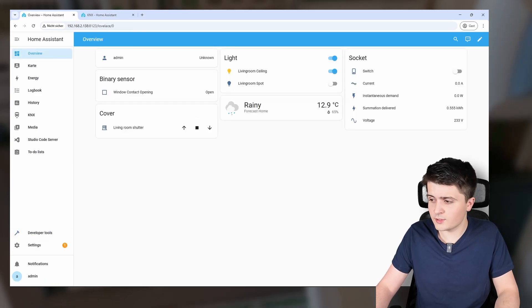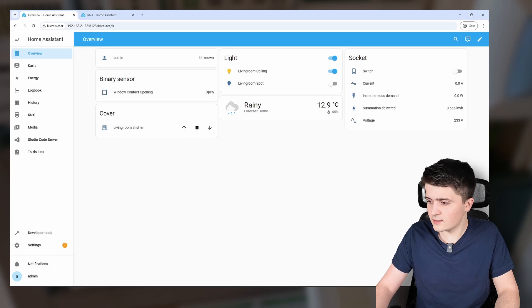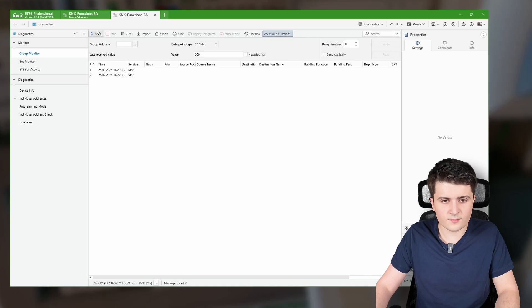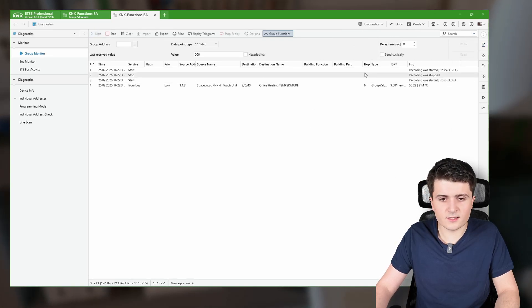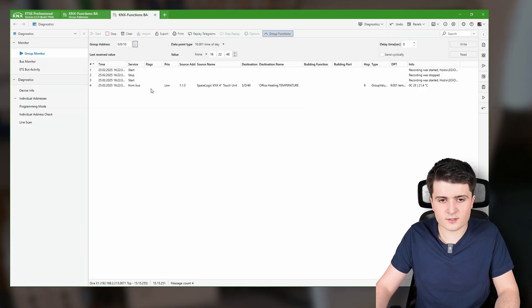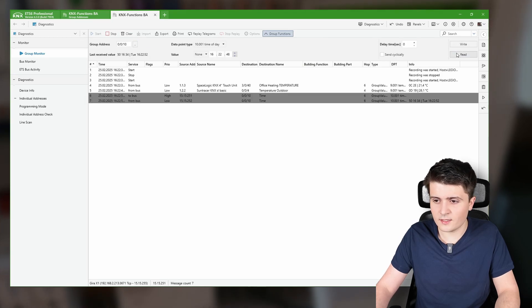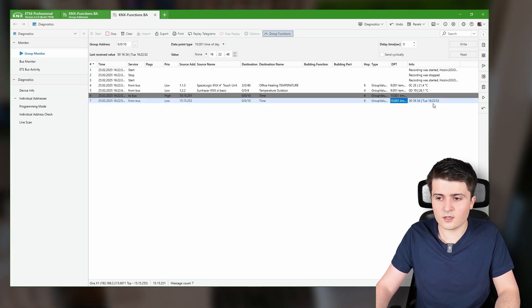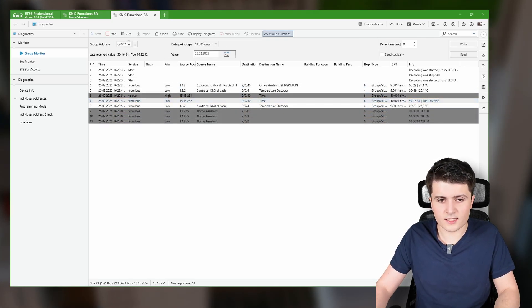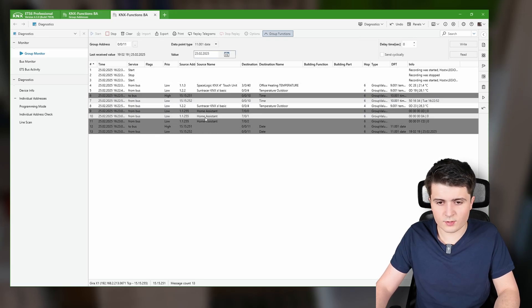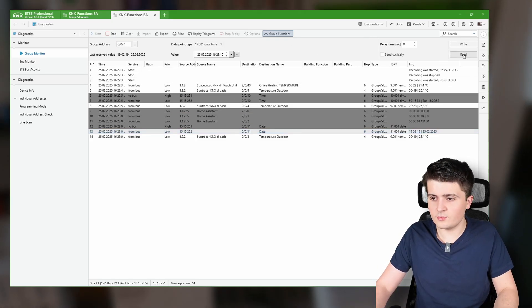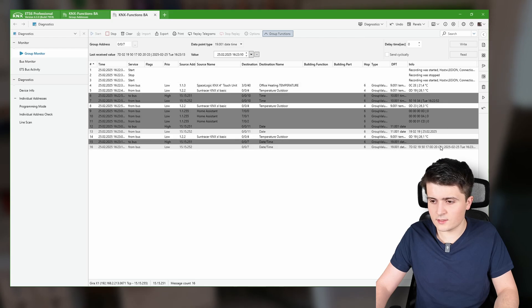I'll head over to developer tools, check the config, and restart KNX. Then we can verify it in ETS6 by opening diagnostics. If I send a read request to address 0010 (time), we get 16:22 — the current time. We can get the current date as well, and sending a read request to date-and-time gives us both date and time together.